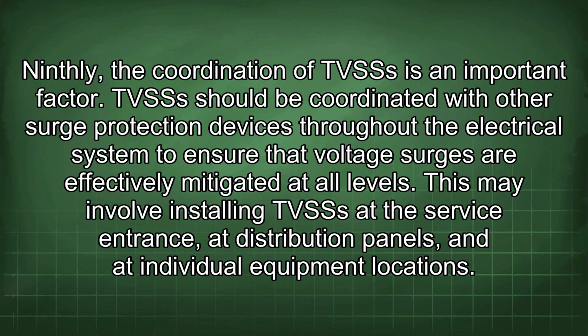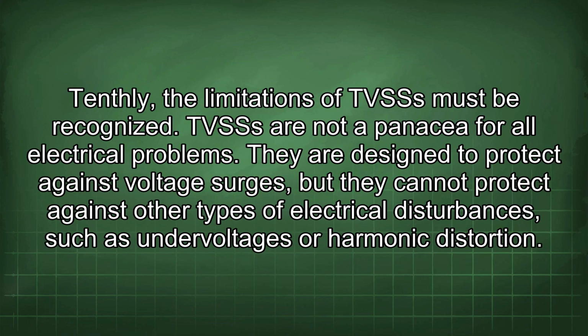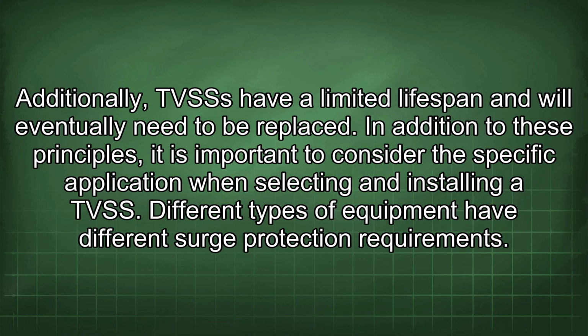Ninthly, the coordination of TVSSs is an important factor. TVSSs should be coordinated with other surge protection devices throughout the electrical system to ensure that voltage surges are effectively mitigated at all levels. This may involve installing TVSSs at the service entrance, at distribution panels, and at individual equipment locations. Tenthly, the limitations of TVSSs must be recognized. TVSSs are not a panacea for all electrical problems. They are designed to protect against voltage surges, but they cannot protect against other types of electrical disturbances such as undervoltages or harmonic distortion. Additionally, TVSSs have a limited lifespan and will eventually need to be replaced.